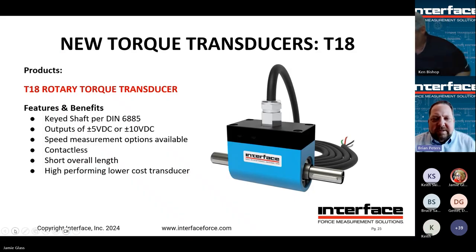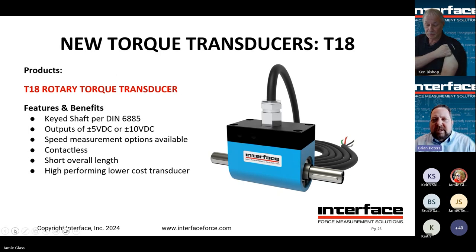On the torque side, our new T18 is an addition to our very popular T8 series torque transducer. Very similar in delivering fantastic reliability and performance of a contactless rotary torque sensor, but at a much lower price point. The unique feature is that this one is available with integral speed measurement — something the T8 was not able to offer. Available in 10 to 100 newton meter range and still delivers a very competitive 0.25% total error, making it easier without needing a separate encoder in your test stand setup.